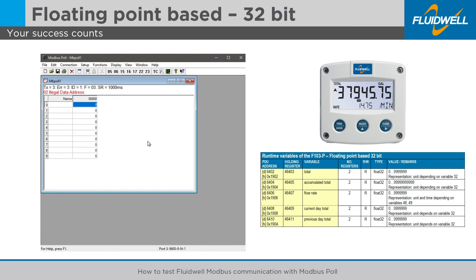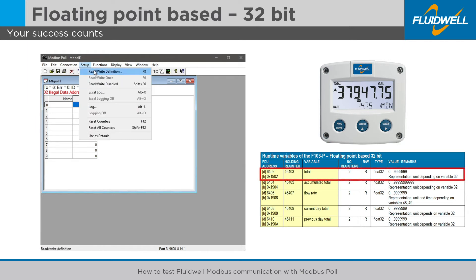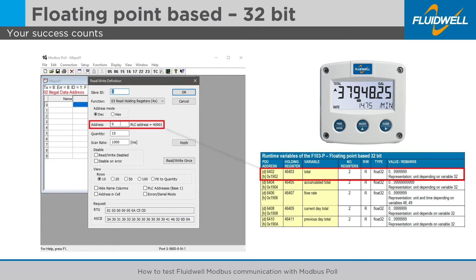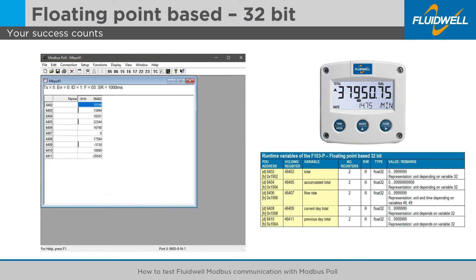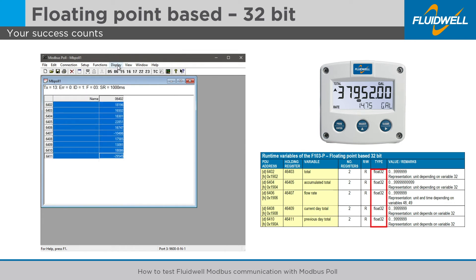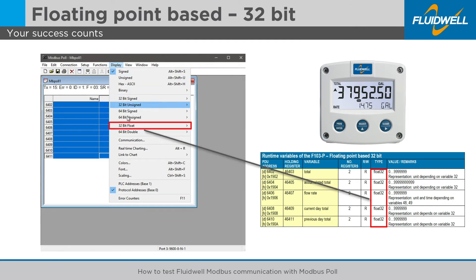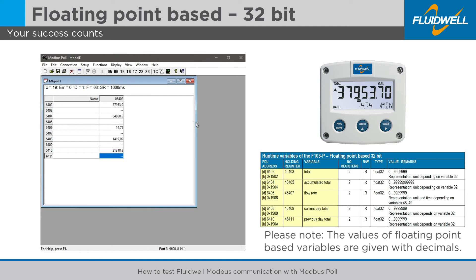For a floating point based 32-bit read of the total accumulated total, flow rate and daily totals, select the corresponding table in the manual. The table shows the first PDU address of 6402 and the total number of registers of all variables is 10. Apply the 32-bit float data type with Big Endian register order for a correct reading. Please note, the values of floating point based variables are given with decimals.